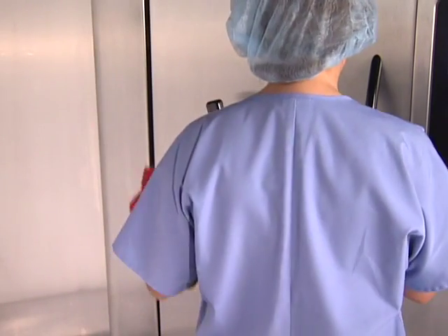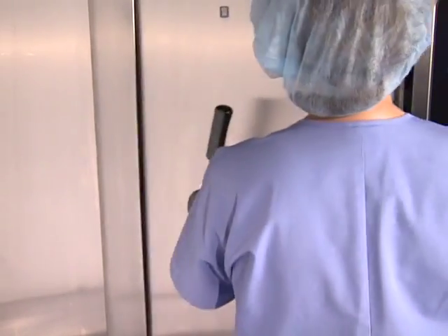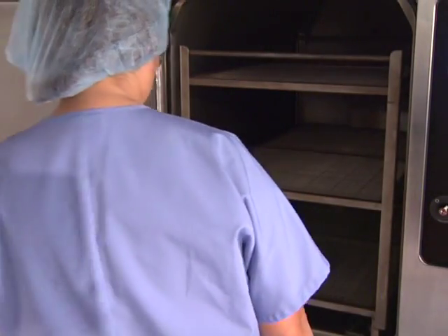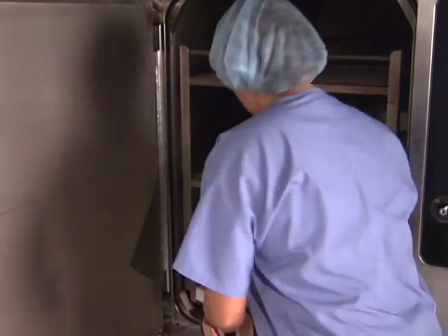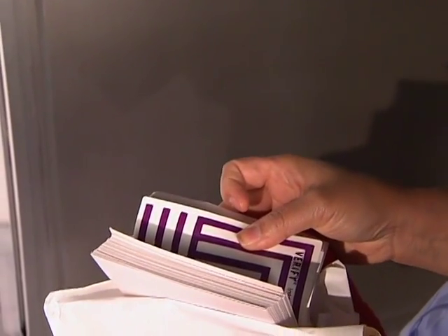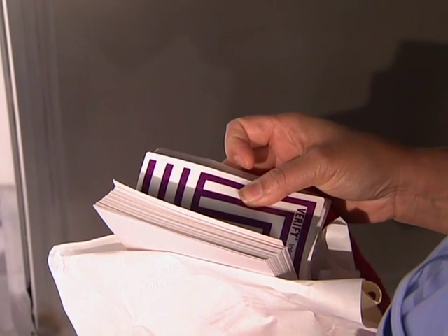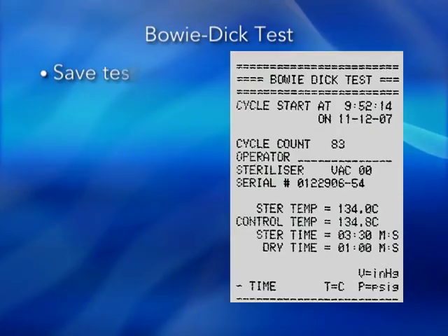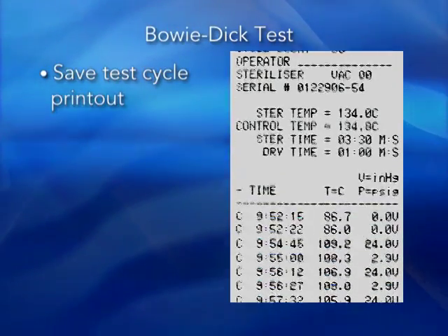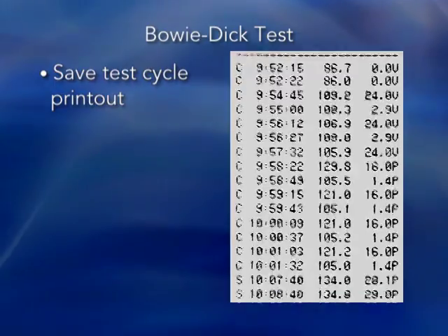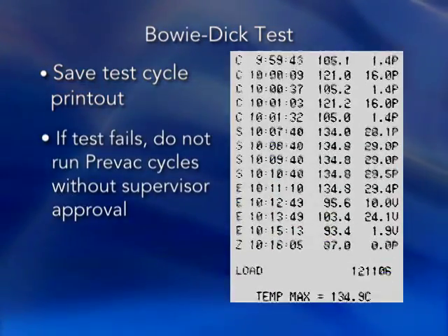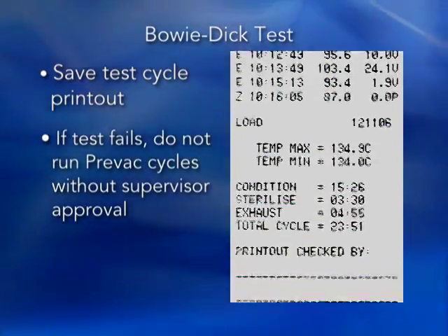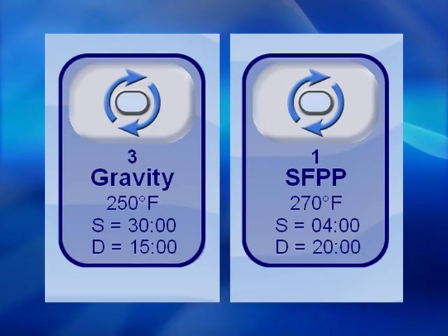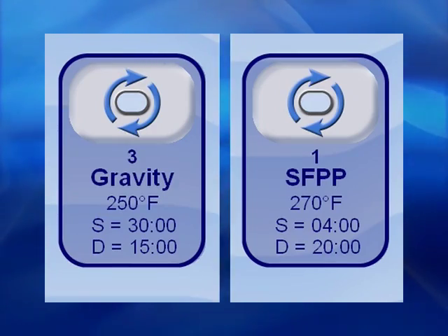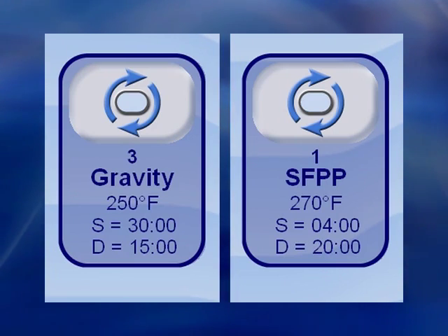At the conclusion of the cycle, put on your personal protective equipment, open the chamber door, and carefully remove and open the DART test or Bowie-Dick test pack. Examine the test sheet indicator for complete and uniform color change. Compare the results to your wall chart, which will help you interpret the test properly. The entire cycle is also documented on the test cycle printout. Report result failures to your supervisor. Do not run the sterilizer with pre-vacuum cycles until approved by your supervisor. Gravity or SFPP cycles may still be used in the event of a Bowie-Dick test failure.